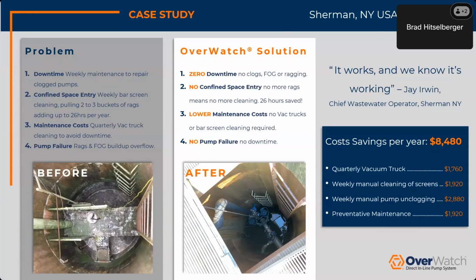And what they had was the picture on the left. To picture what was going on there, it was a dry pit, wet pit scenario. They had a bar screen down there, and you can see those pictures. There's rags building up and building up and building up. This is a municipality where there's not a lot of people in the town, and there's one full-time person that works there, and then they had a part-time person that worked at the wastewater treatment plant. So along with doing all their process tasks that they had to do on a daily basis, they had to worry about this one pump station.